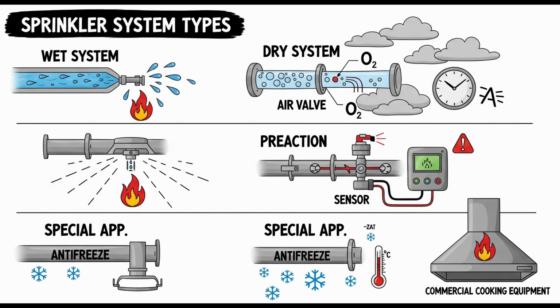A listed indicating valve is also required in the water supply line that's dedicated solely to these cooking equipment and ventilation sprinklers nozzles. Yes, it allows this specialized subsystem to be isolated for maintenance without shutting down the main building sprinklers. And just like other systems using sprinklers with small orifices, a listed line strainer is required in the supply pipe upstream of any sprinklers or nozzles having K-factors smaller than K2.8 to prevent potential clogging from waterborne debris.